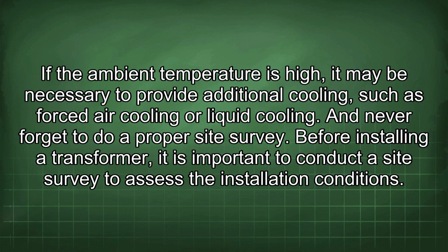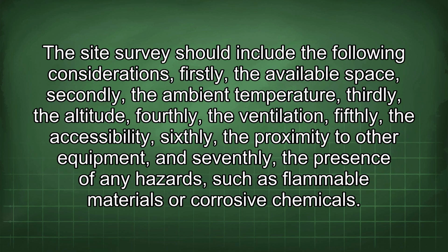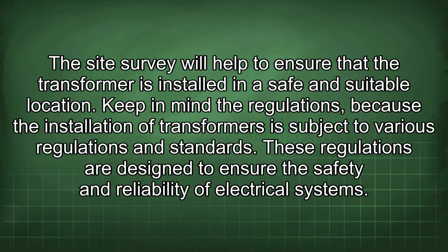Before installing a transformer, it is important to conduct a site survey to assess the installation conditions. The site survey should include the following considerations. Firstly, the available space. Secondly, the ambient temperature. Thirdly, the altitude. Fourthly, the ventilation. Fifthly, the accessibility. Sixthly, the proximity to other equipment. And seventhly, the presence of any hazards, such as flammable materials or corrosive chemicals. The site survey will help to ensure that the transformer is installed in a safe and suitable location.